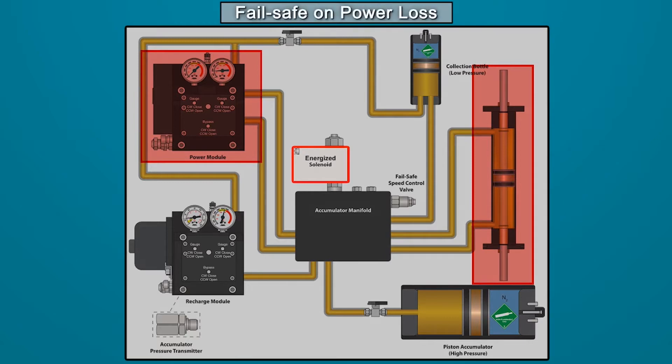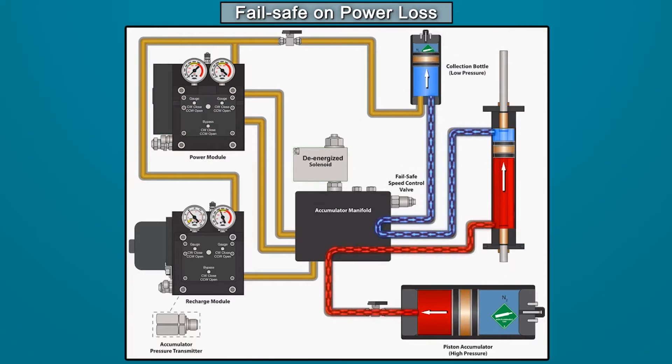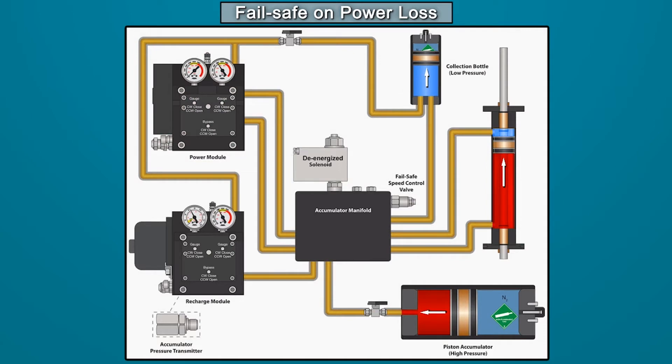On a trip or loss of power condition the solenoid valve is de-energized causing it to open. The accumulator pushes oil into the connected hydraulic cylinder while the pressurized collection bottle provides a place for the displaced cylinder volume to empty into. This moves the connected valve or device to the fail-safe position.